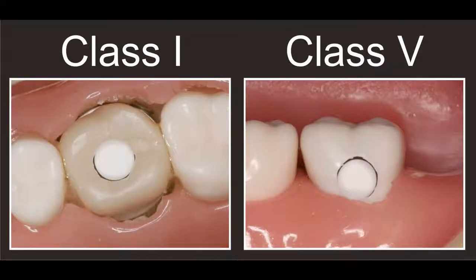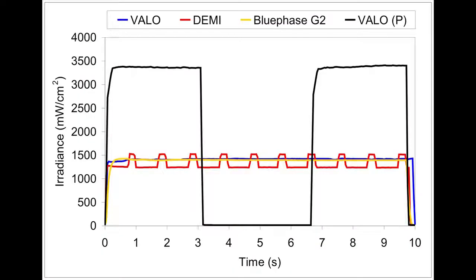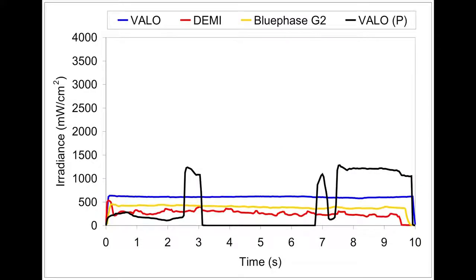Here we can see the location of the sensors described in the article. The sensor in the Class I location was 4 millimeters from the cusp tip, and in the Class V location the sensor was 2 millimeters from the facial surface. One operator used the curing light to its maximum potential, delivering a very uniform irradiance in the Class V location. Another operator was less steady, delivering a non-uniform and low amount of irradiance to the Class V detector.